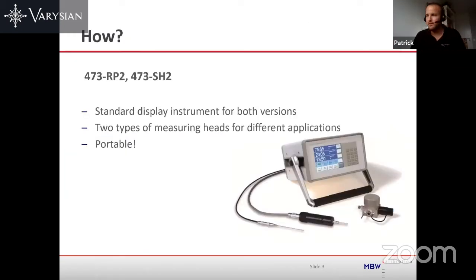The instrument that we recommend, which is basically our workhorse, so MBW sells a whole range of products. The 473 is, let's say, our workhorse. It's our portable, transportable dew point mirror, also called the chilled mirror hygrometer, and it works as a reference measurement instrument for humidity and temperature measurements. The main advantage of this instrument is that it's highly adaptable to whatever climate chamber or humidity generator you might already have. So it's a wonderful way to upgrade what you have and add a highly accurate, traceable measurement to your lab.